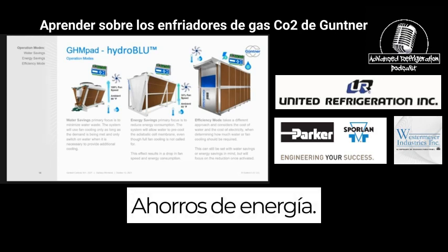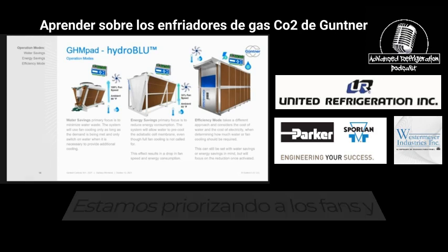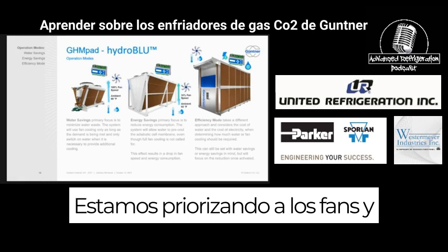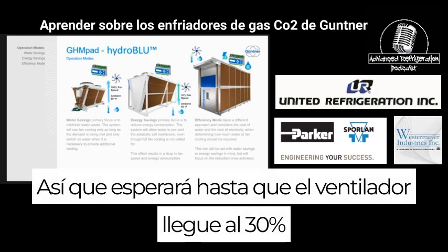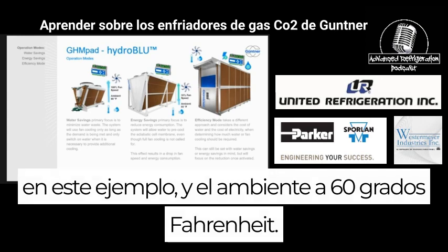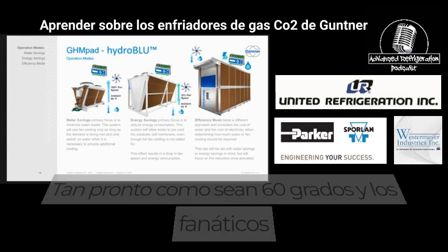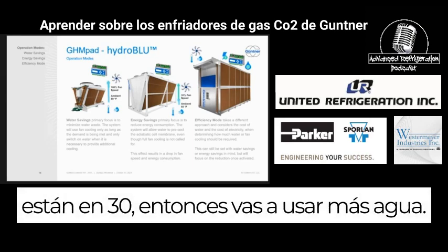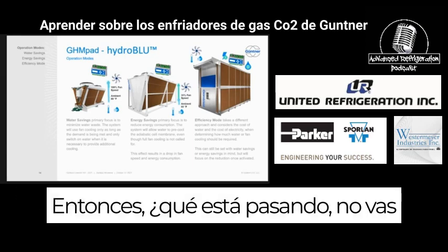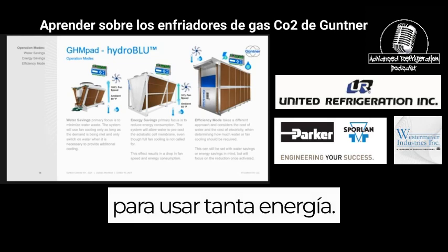Energy savings, we're prioritizing the fans and we are using more water. It's going to wait till the fans get to 30% in this example and the ambient to be 60 degrees Fahrenheit. As soon as it's 60 degrees and the fans are at 30, then you're going to use more water. So what's happening is you're not going to use as much energy.